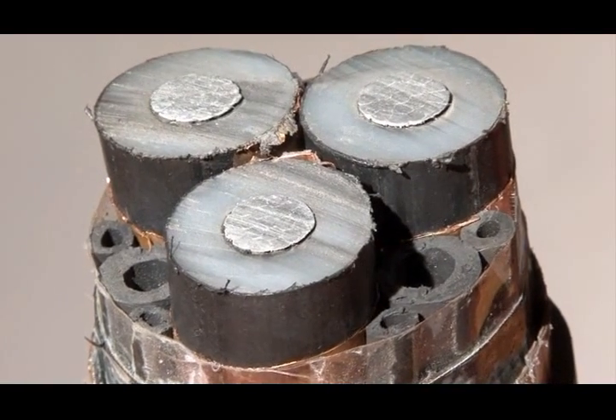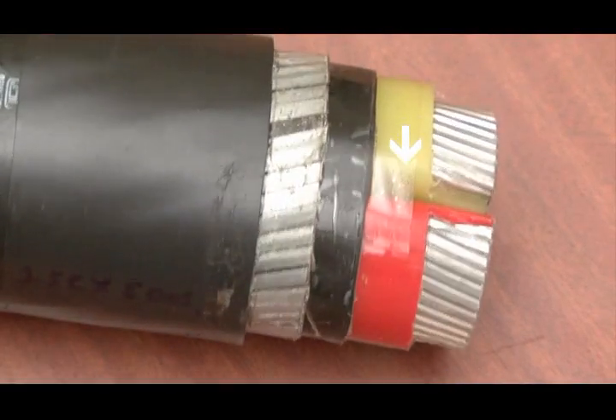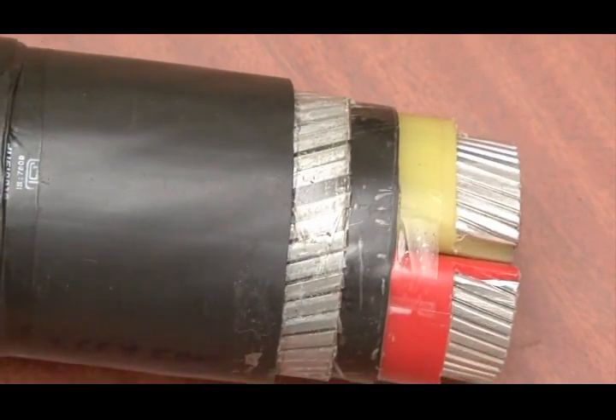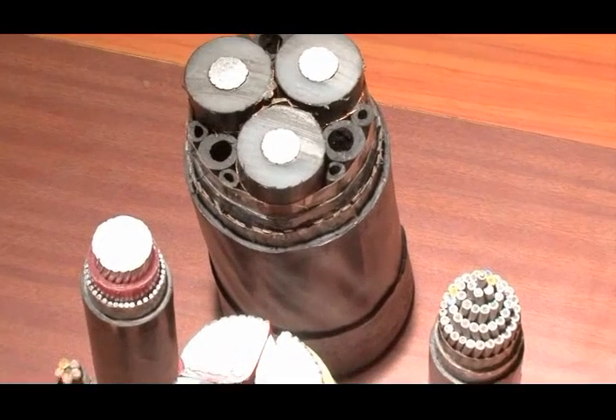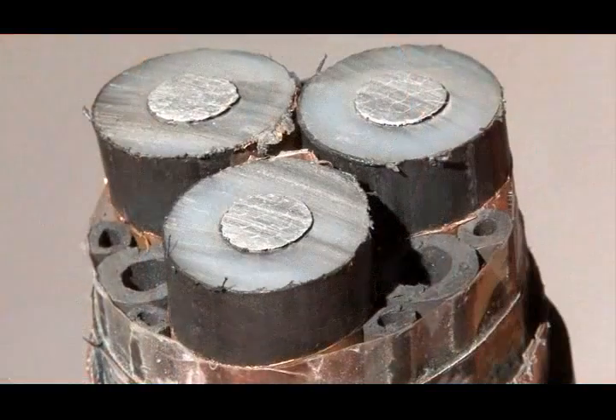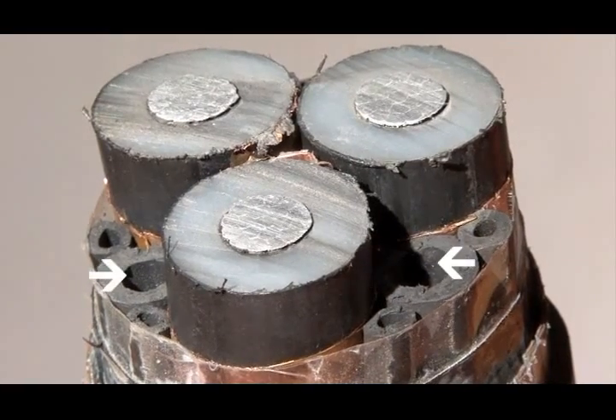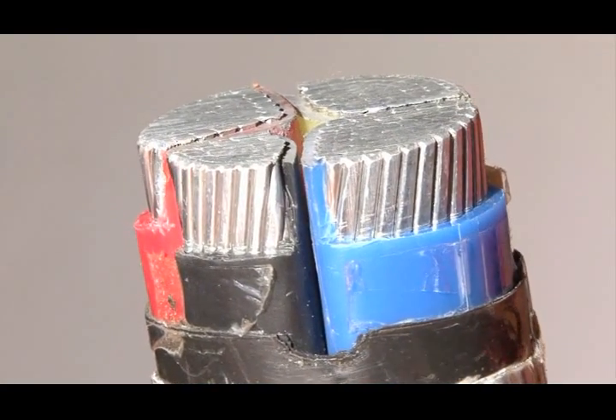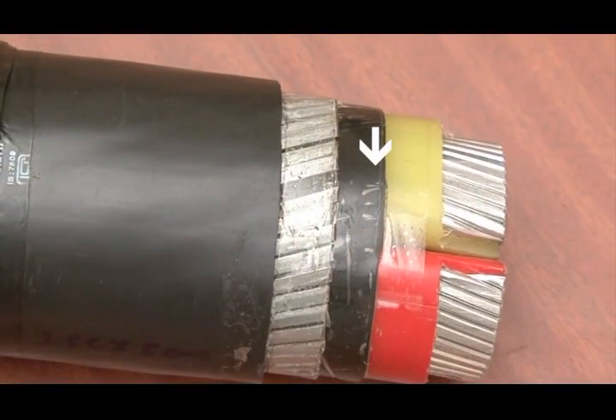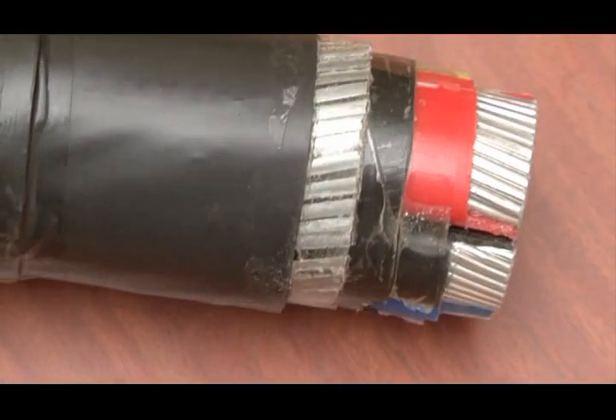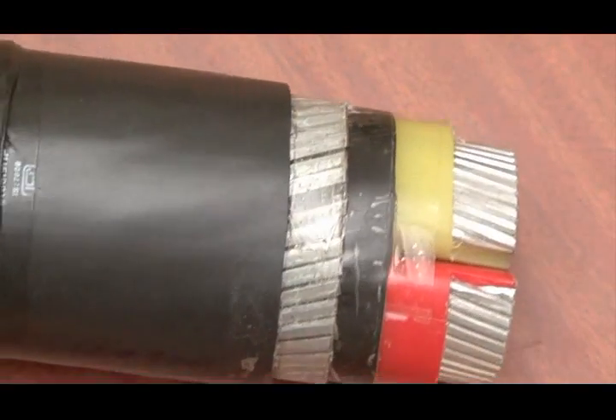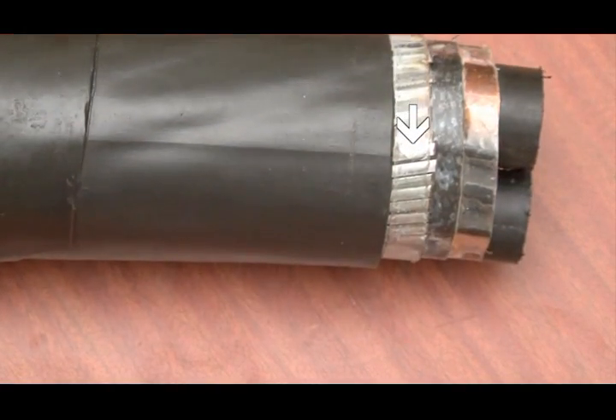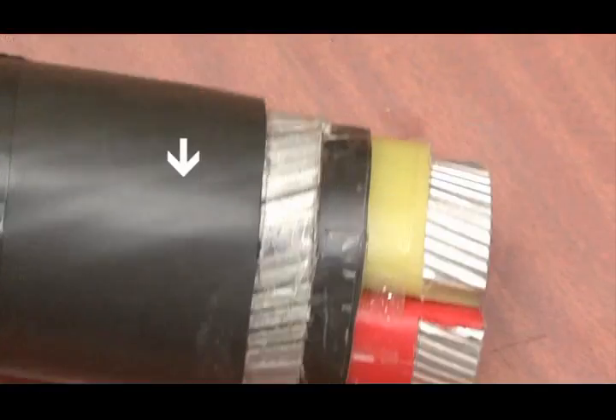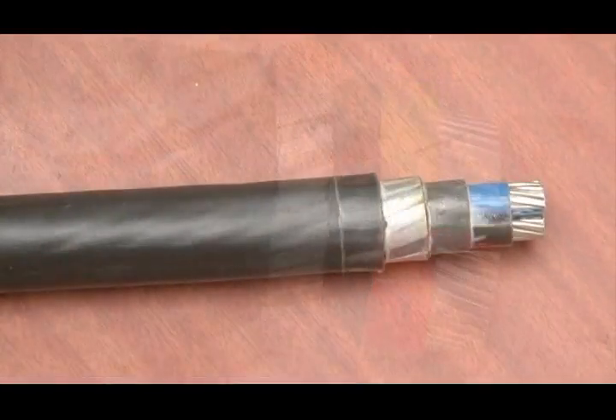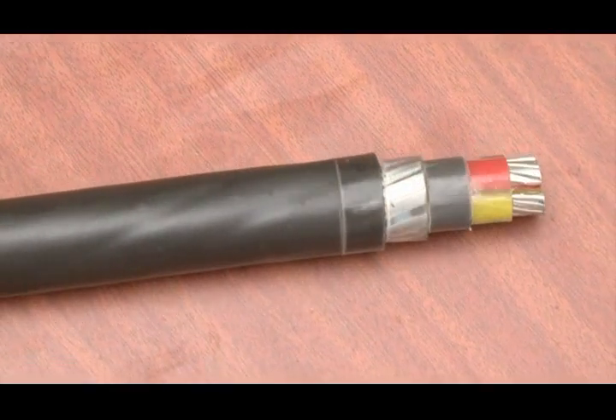High-quality PVC base compound is used for insulating power cables and high-quality cross-linked polyethylene compound is used for insulation of XLPE cables. Multi-core cables are laid up as per the color scheme and the interstices are filled up if needed to make the cables cylindrical. All cables with 2 or more cores are provided with a common cover called inner sheath made of PVC compound or thermoplastic. Multi-core cables are provided with armoring, which is made up of galvanized round steel wire over the inner sheath. Outer sheath is extruded over the armoring. This is always black in color to resist the outdoor exposure.